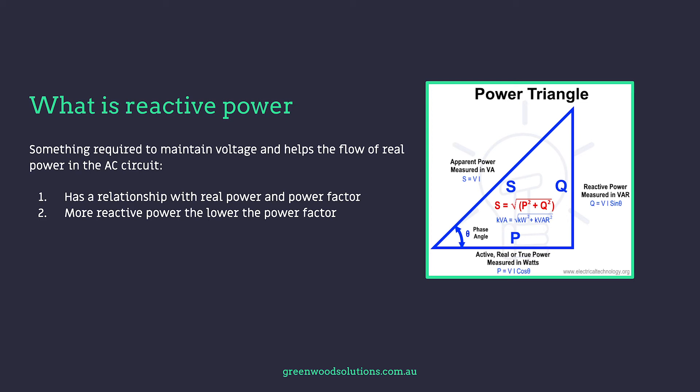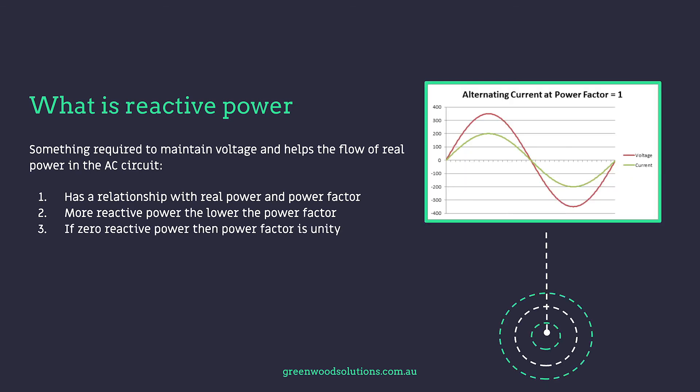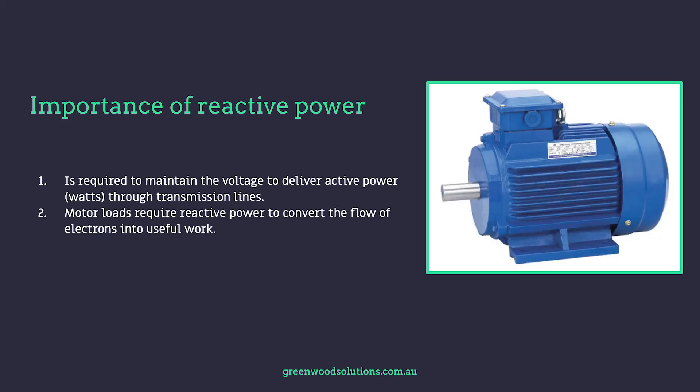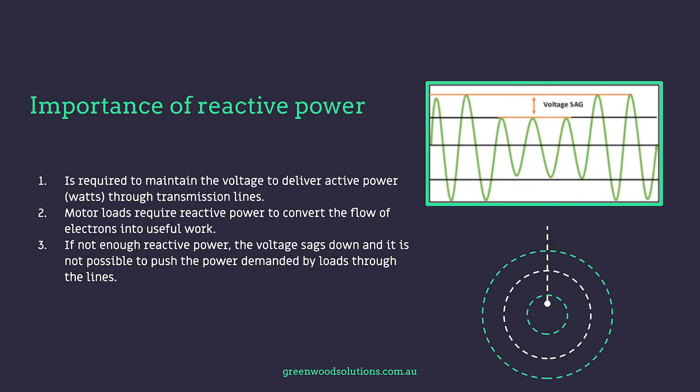More reactive power means a lower power factor. If there's zero reactive power, then the power factor is unity — but in reality, this never exists, because all sites are made up of loads that are resistive, inductive and capacitive. Reactive power is not wasted power — it is important. It's required to maintain the voltage to actually deliver power through the transmission lines. Motor loads require reactive power to convert the flow of electrons into useful work. If there's not enough reactive power, the voltage sags down and it is not possible to push the power demanded by loads through the transmission lines. There always has to be a certain percentage of reactive power.